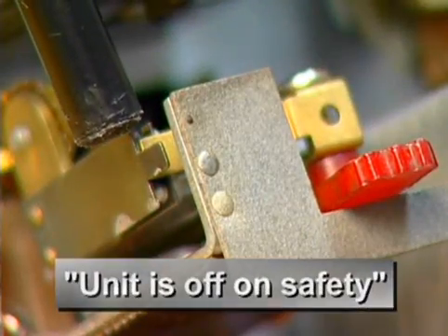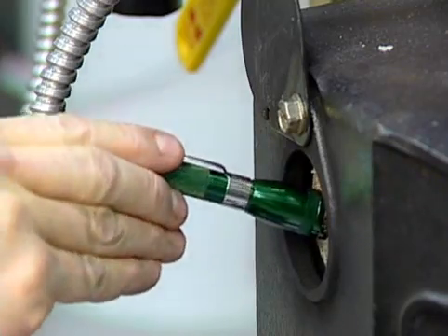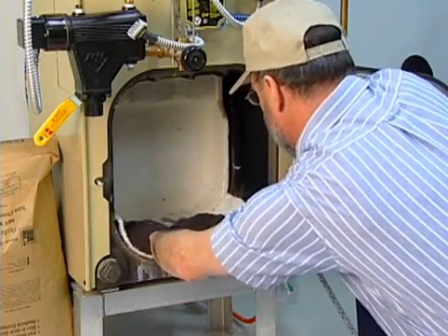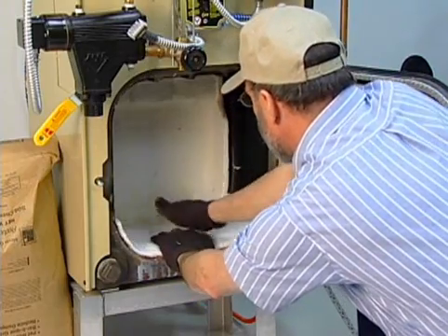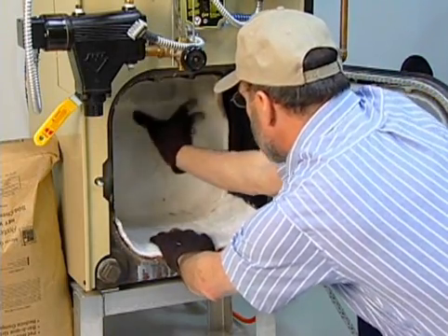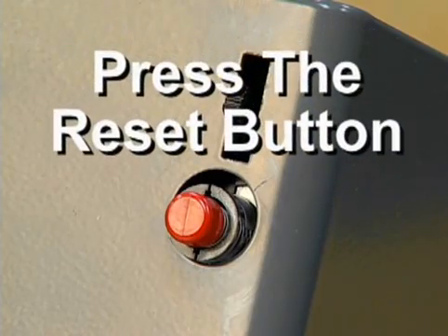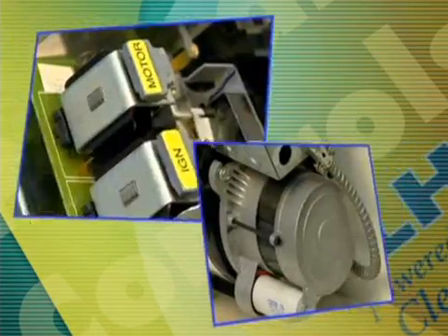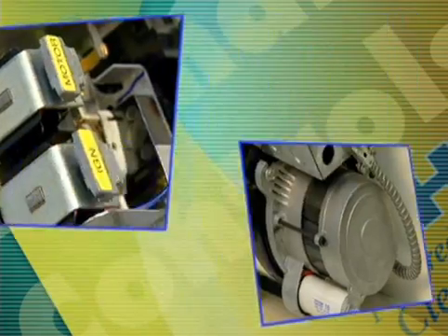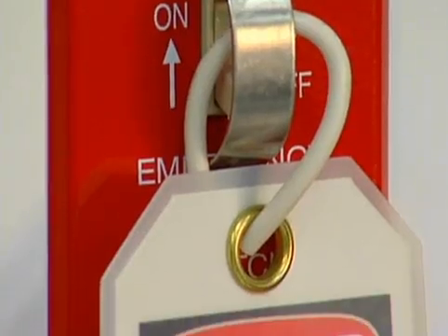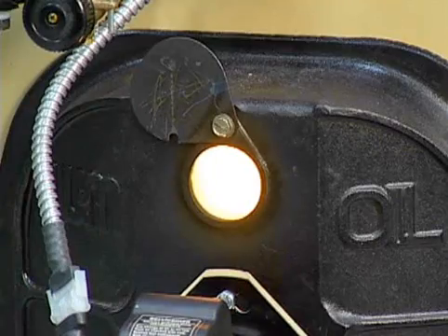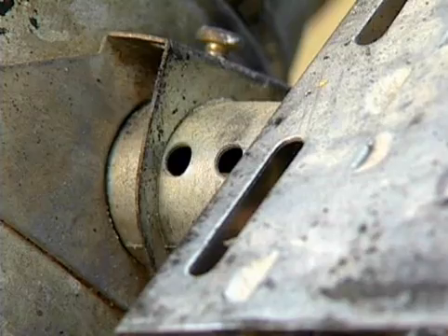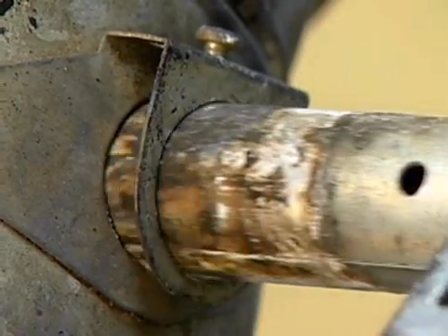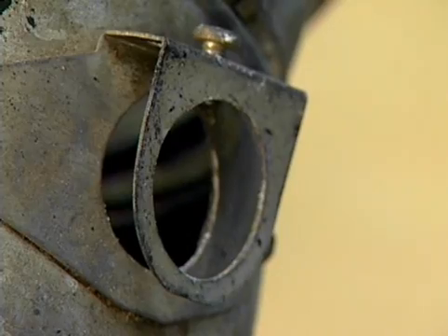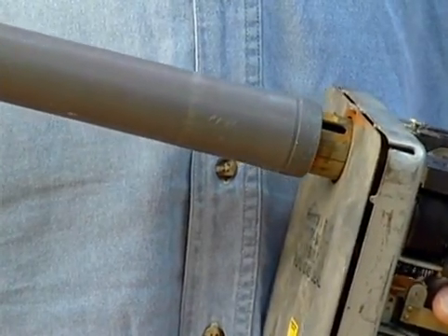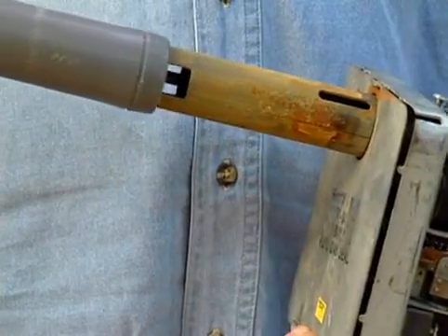If the primary is off on safety, check the combustion chamber. If it contains excess oil, follow your company's procedures to eliminate the oil. Never attempt to fire an oil burner into a chamber saturated with oil. If the chamber is free of excess oil, press the reset button. If the relay energizes but the burner motor doesn't spin, turn off the electrical supply and check the electrical connections and the burner motor. If the burner runs and shuts off on safety, check the bimetal sensor. It may be coated with soot, which prevents it from sensing the temperature in the flue. Clean the bimetal and continue your troubleshooting to find out why the unit is sooting.